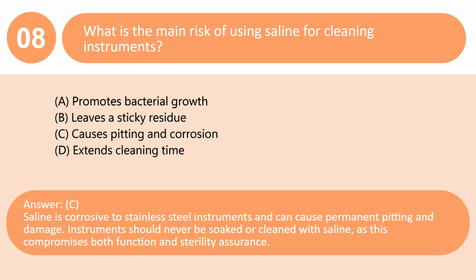Saline is corrosive to stainless steel instruments and can cause permanent pitting and damage. Instruments should never be soaked or cleaned with saline, as this compromises both function and sterility assurance.